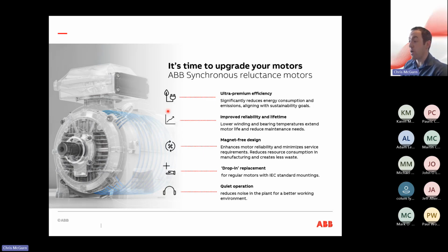They have improved bearing lifetimes. They have reduced maintenance needs. The SynRM motor, which sometimes is compared to different technologies, has a magnet-free design, which enhances motor reliability and minimizes service requirements. And also, from a circularity point of view, it has fewer internal components that can come from less ethical places. So it doesn't require any special parts that some other permanent magnet motors may require, for example.